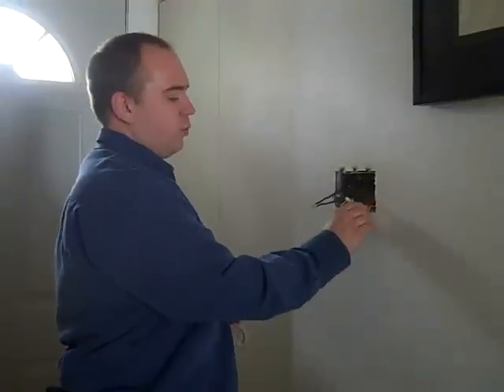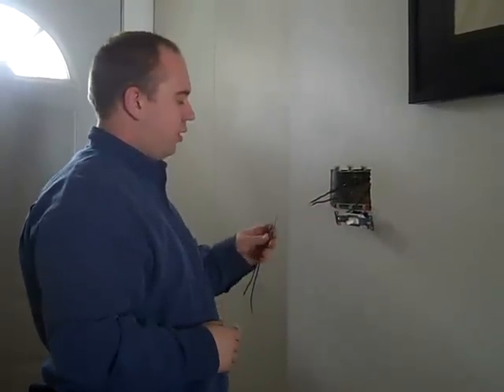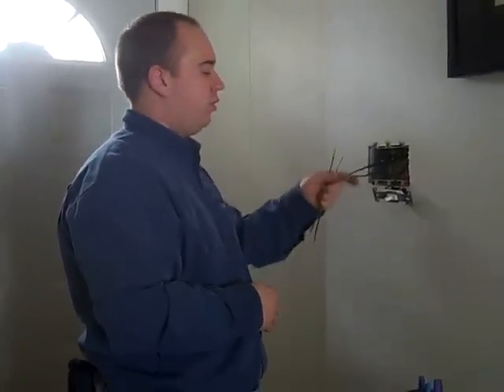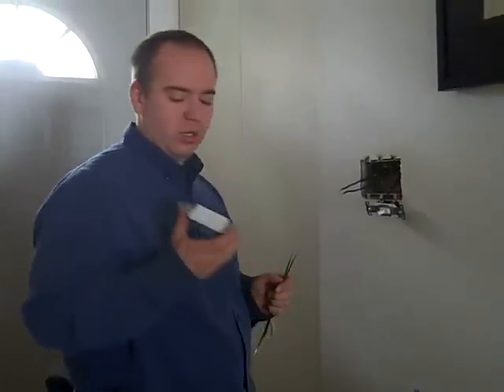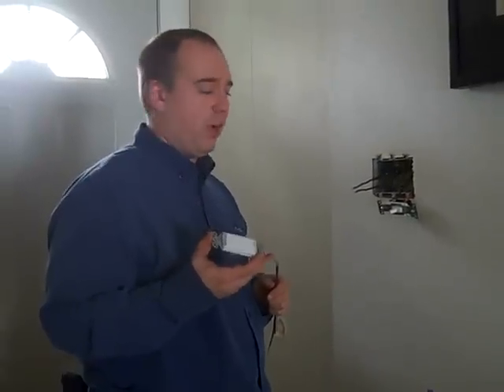So just putting a CO/ALR switch on is our option one. Option two is adding copper tails and making sure that we're using appropriate loaded marrettes — aluminum-rated marrettes — so that we can add a copper wire to the aluminum. That way we can go ahead and use our new Decora-style switches, which a lot of people are preferring nowadays, but they are not rated for aluminum wire.